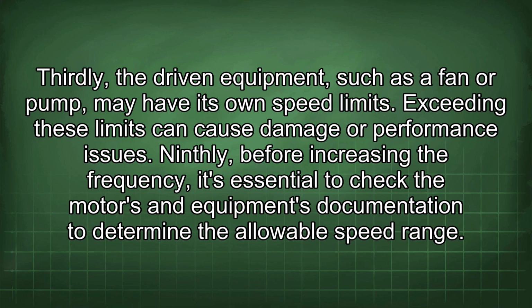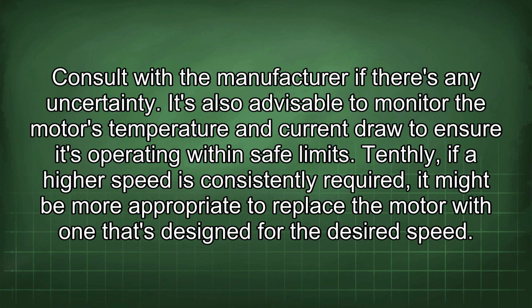Ninthly, before increasing the frequency, it's essential to check the motor's and equipment's documentation to determine the allowable speed range. Consult with the manufacturer if there's any uncertainty. It's also advisable to monitor the motor's temperature and current draw to ensure it's operating within safe limits.